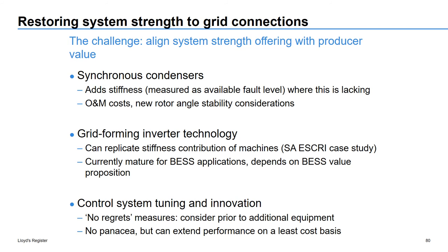At a certain cost, which may also add to O&M requirements, and adding an additional rotor angle stability mode into the system where the wider area implications of that need to be considered by the system operator. We have the grid forming inverter technology, which can replicate that stiffness contribution through an electronic source. We have a demonstration of that in the NEM currently in South Australia with the ESCRI project.